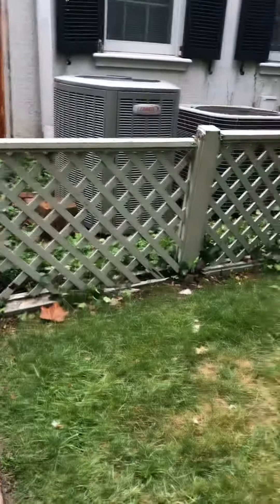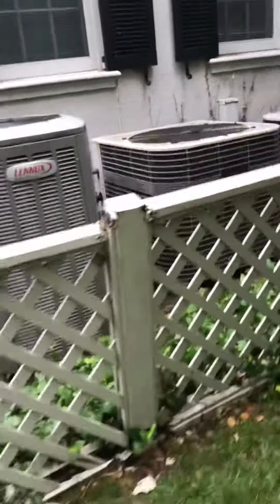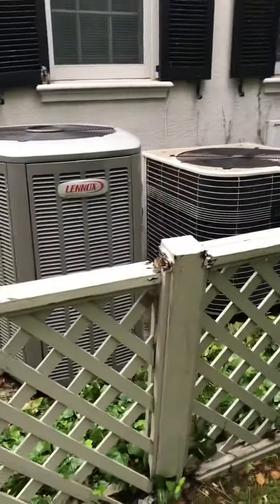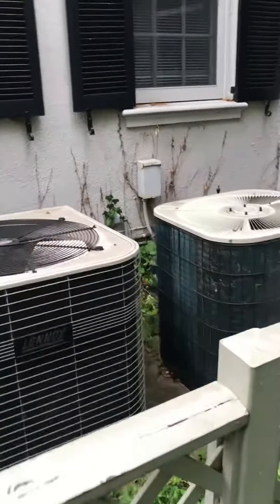Looking at the house from the street, we've got three units lined up. The one we're interested in that handles the main level is the one closest to the house — it's a 35-year-old BDP unit. We're going to come back in the same spot; you can see there's concrete there, so we'll bring a new pad, put the new unit on the new pad, new fuse disconnect, new whip.